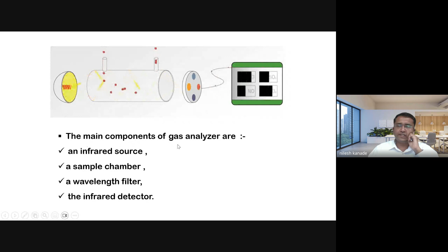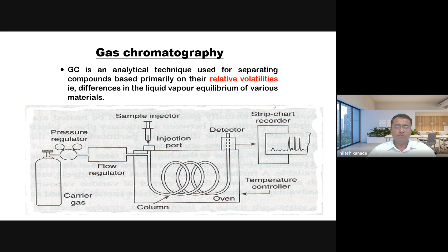So you see, the main components of these gas analyzers are the infrared source, sample chambers, wavelength filters, and the infrared detectors. Another one is gas chromatography. It is a very renowned and very old technology, and it is very complex as well. In most of the process industries, gas chromatography measuring principles are used because it can measure the maximum number of gases in one analyzer. GC is an analytical technique used to separate the components based primarily on their relative volatility, that is the difference in the liquid vapor equilibrium of liquid materials. This technology is used for gas and liquid as well.